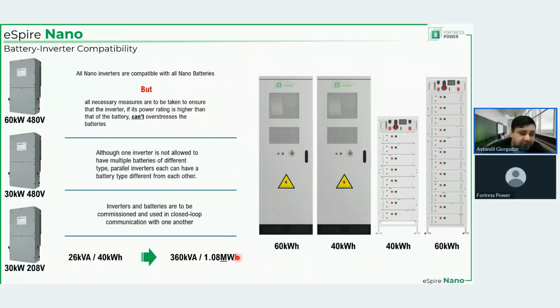So where does this number come from? Well, each inverter can have three batteries connected to it. So 3 times 60, that's 180. And you can have 6 of these inverters, each with 3 60 kilowatt hour units. And that gives you slightly over 1 megawatt hour.